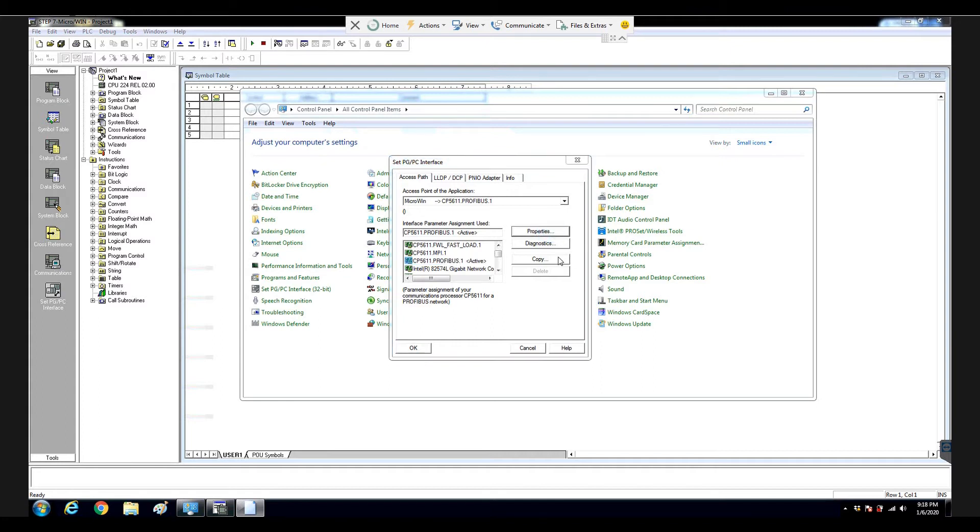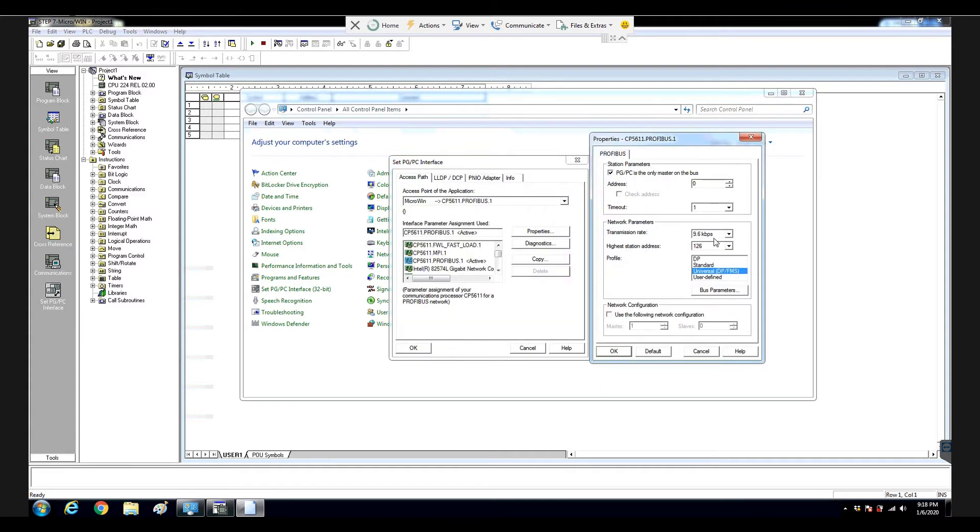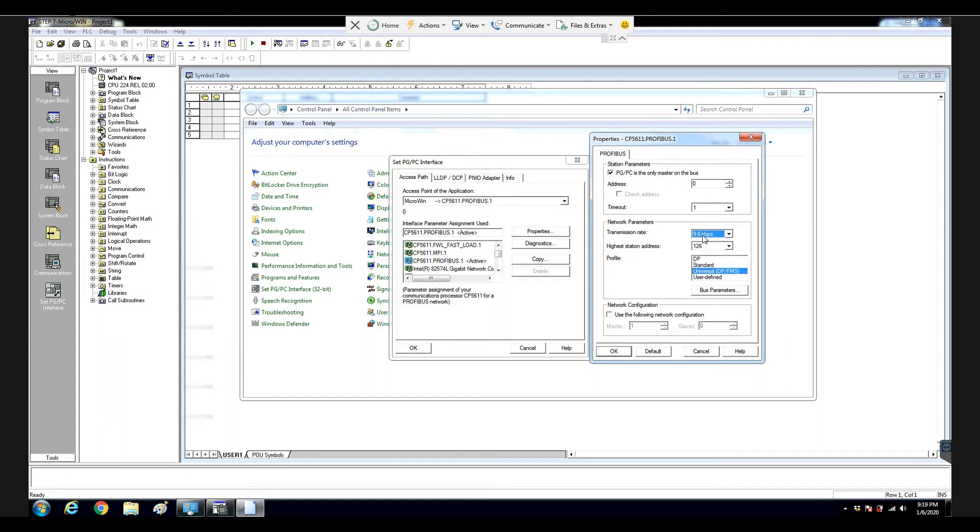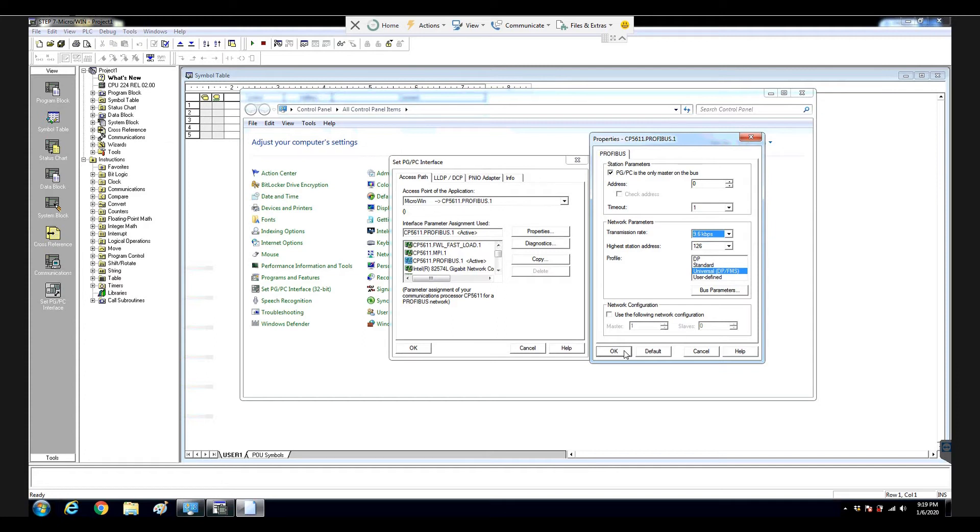So let's hit the properties. And from here, we select transmission rate 9.6, but keep in mind here, by default, because that is a Profibus, by default, the profile will select to DP. To allow this CP5611 to communicate for PPI, we can select the Universal DP/FMS, and select the speed 9.6, and if your laptop is only one master station in this bus, you can select check this box, PGPC is the only master on the bus, and hit OK.